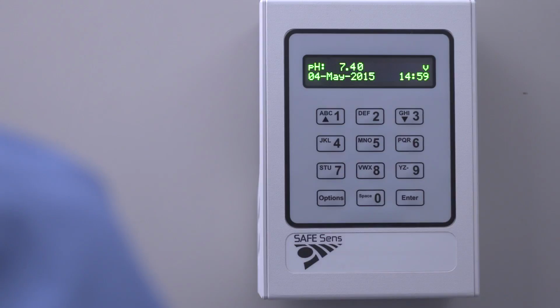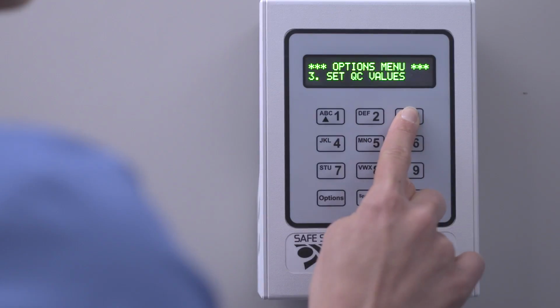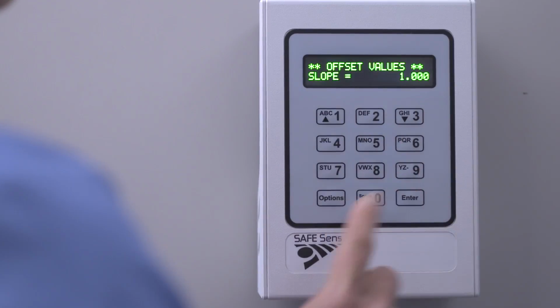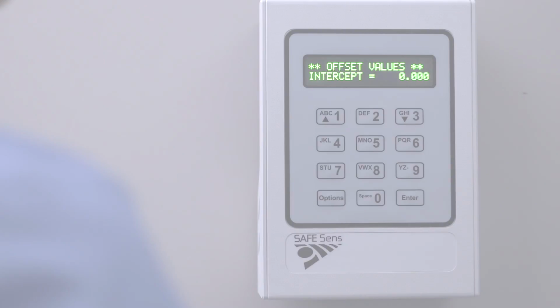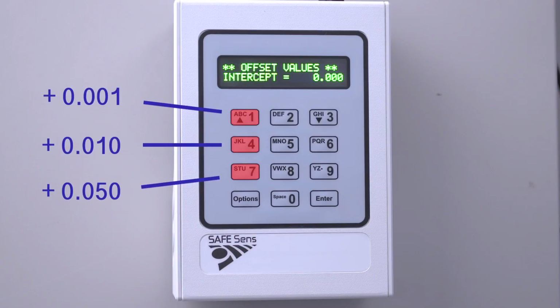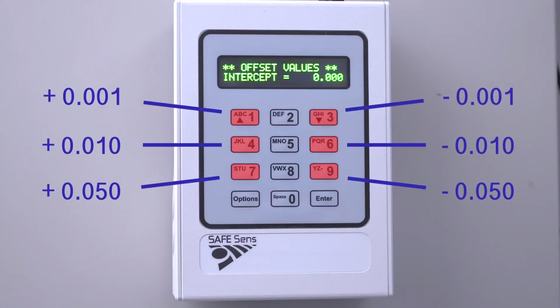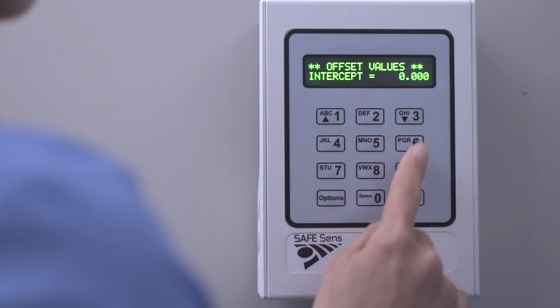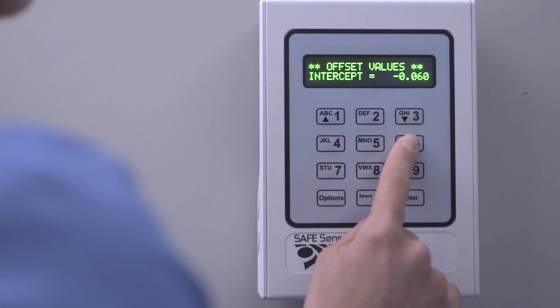On the SafeSense, end your test by pressing Options, then press Options again at the home screen. Use the down arrow to navigate to the offset values and press Enter. Leave the slope as 1 and press Enter. Now use the buttons on the instrument to adjust the intercept. The 1, 4, and 7 keys adjust the value upwards by different amounts, and the 3, 6, and 9 keys adjust the value downwards. We are entering negative 0.09 for our offset value.